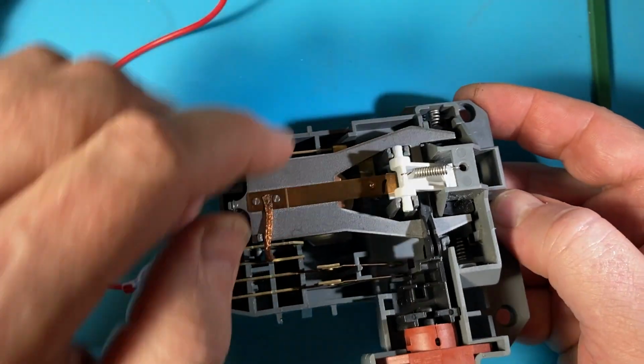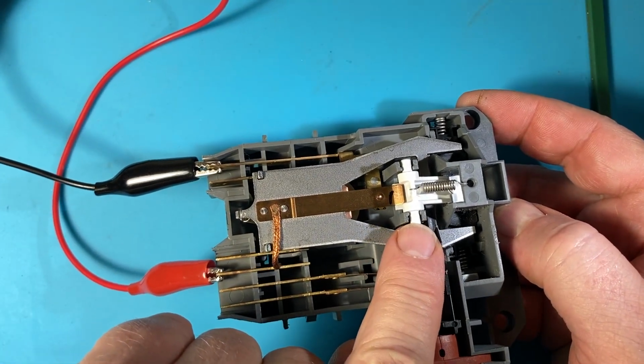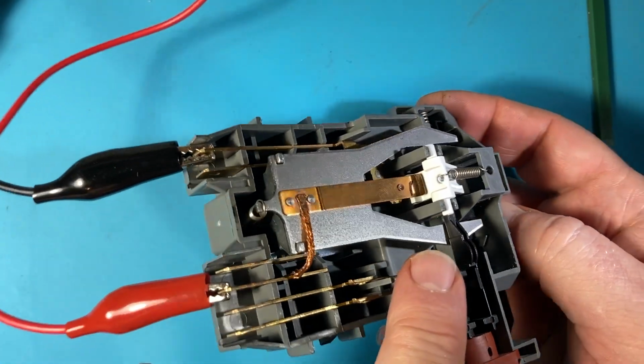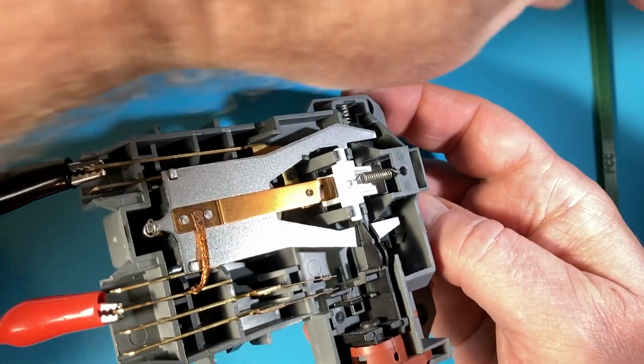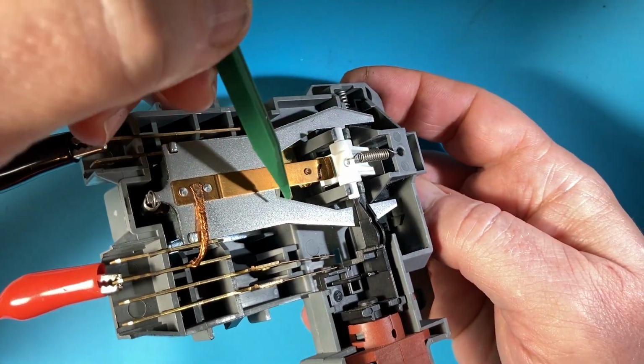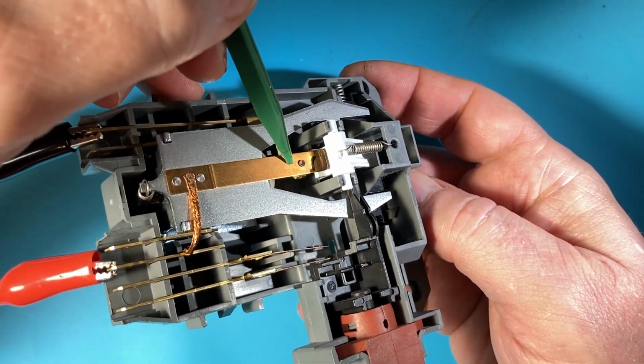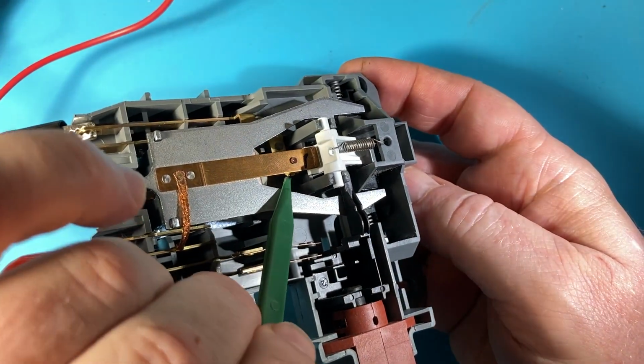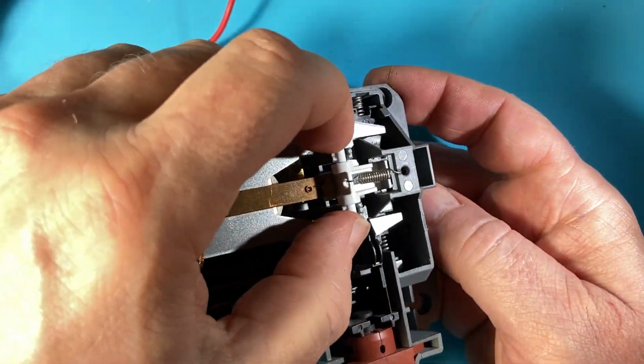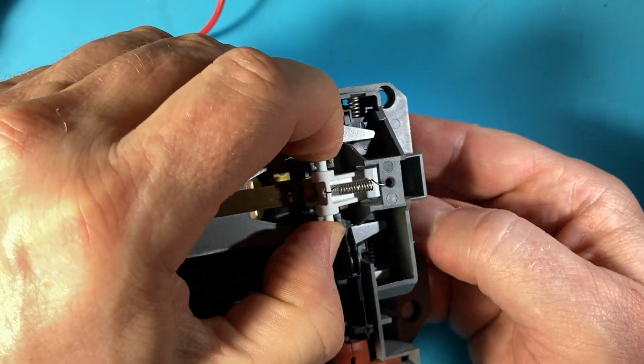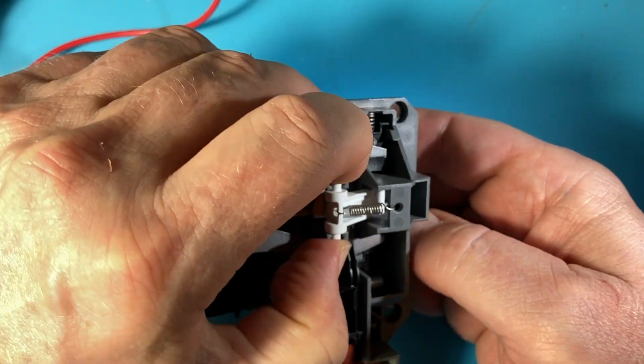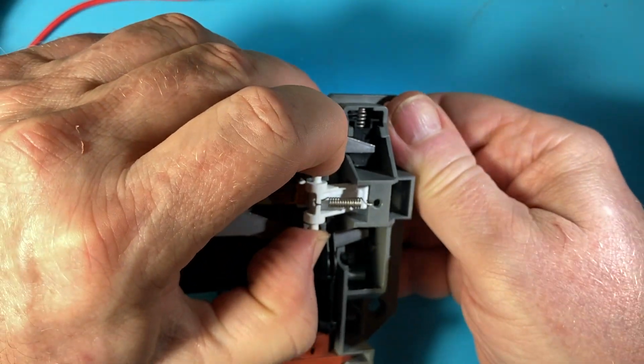When that happens, you'll see this white plastic shoe toggle backward, which will allow this to fall all the way to the contact when the relay is energized. I'm going to hold the ends of this here to keep it, because it's going to go under pressure. I'm going to close the door, or try to close the door.